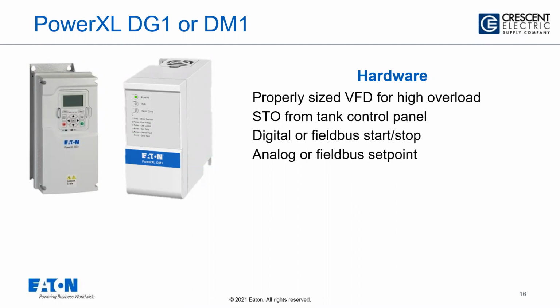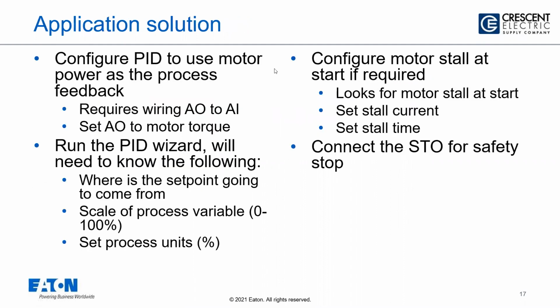One thing is, since these applications are constant torque, the drive has a feature, the flux vector control, within the drive. It offers higher torque even at low speeds or zero speed. So it is a perfect drive for your constant torque application for these types of mixer and blender applications.